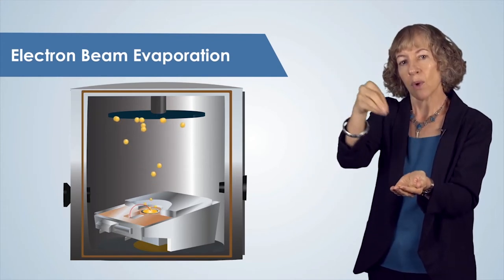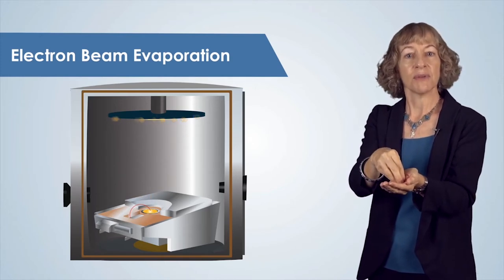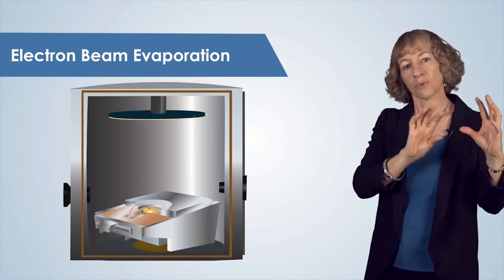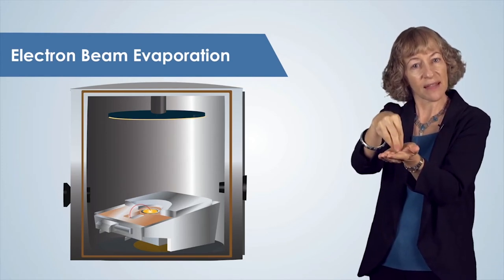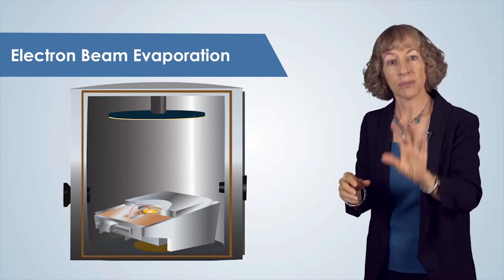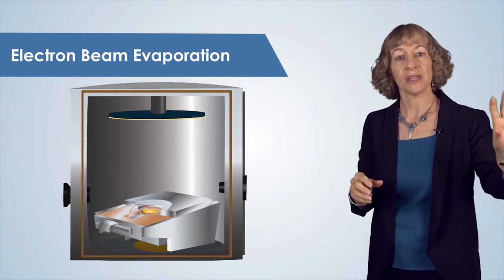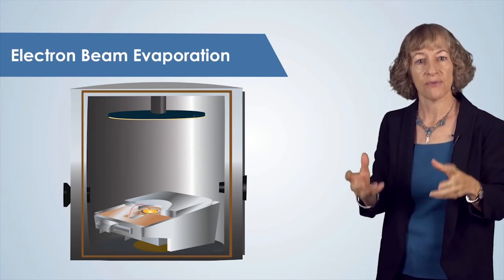This electron beam is well confined, and one of the advantages of e-beam evaporation is that we can rotate different source materials into the path of that electron beam, so that we can deposit multiple materials sequentially without opening the vacuum system, which is also called breaking vacuum or venting.